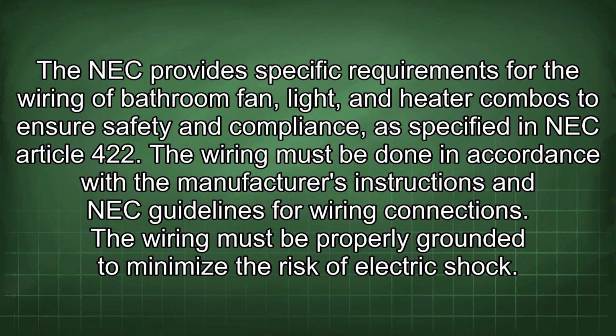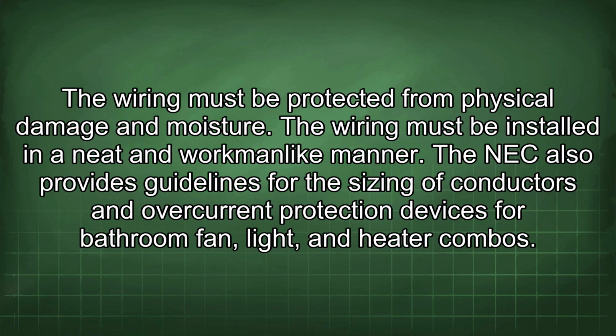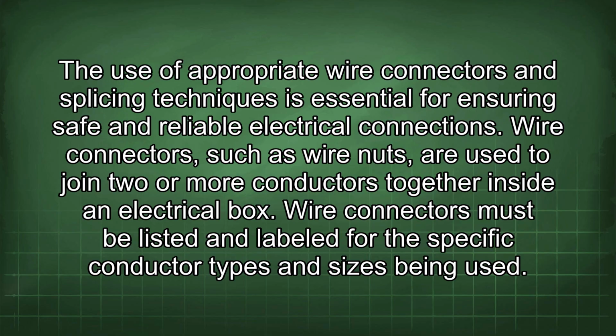The NEC provides specific requirements for the wiring of bathroom fan, light, and heater combos to ensure safety and compliance, as specified in NEC Article 422. The wiring must be done in accordance with the manufacturer's instructions and NEC guidelines for wiring connections. The wiring must be properly grounded to minimize the risk of electric shock. The wiring must be protected from physical damage and moisture. The wiring must be installed in a neat and workmanlike manner. The NEC also provides guidelines for the sizing of conductors and overcurrent protection devices for bathroom fan, light, and heater combos. The use of appropriate wire connectors and splicing techniques is essential for ensuring safe and reliable electrical connections.